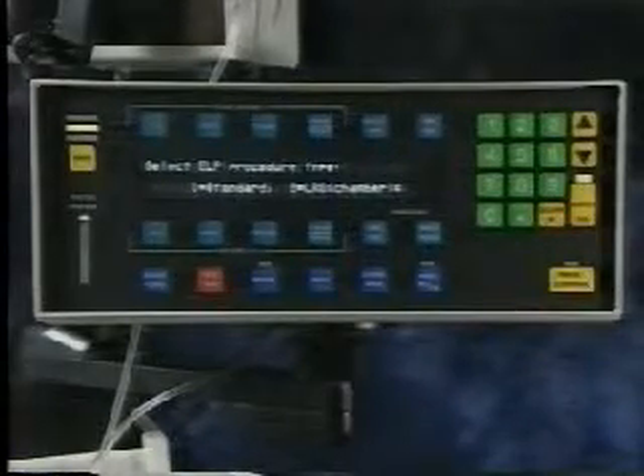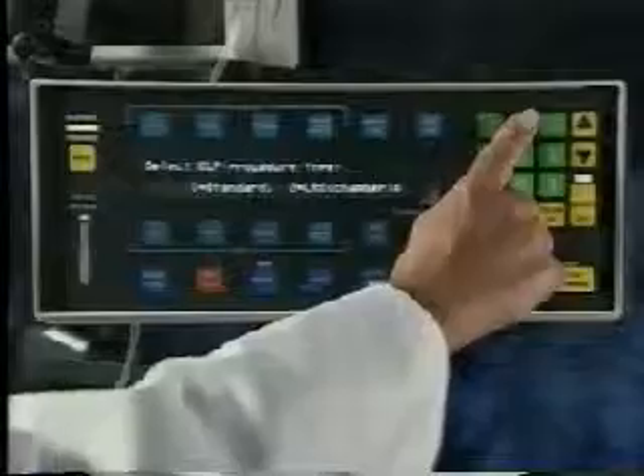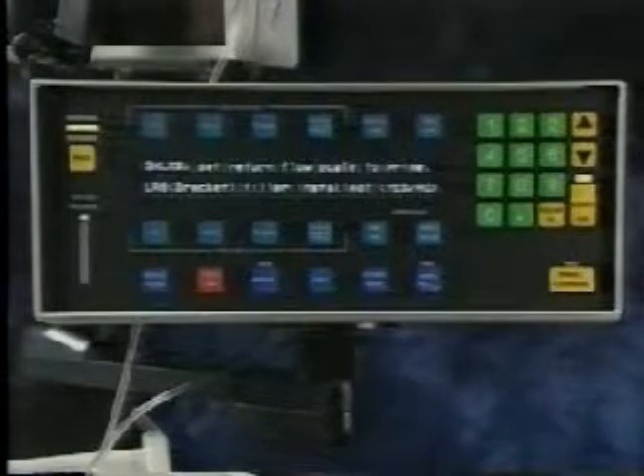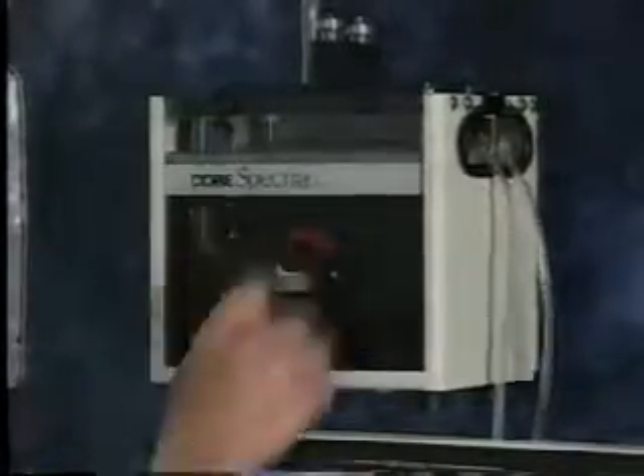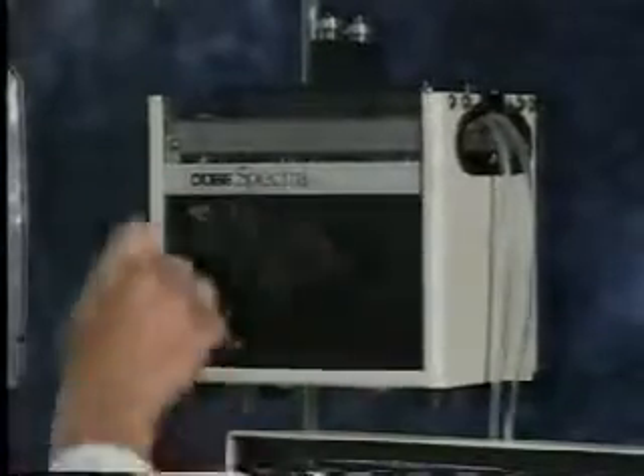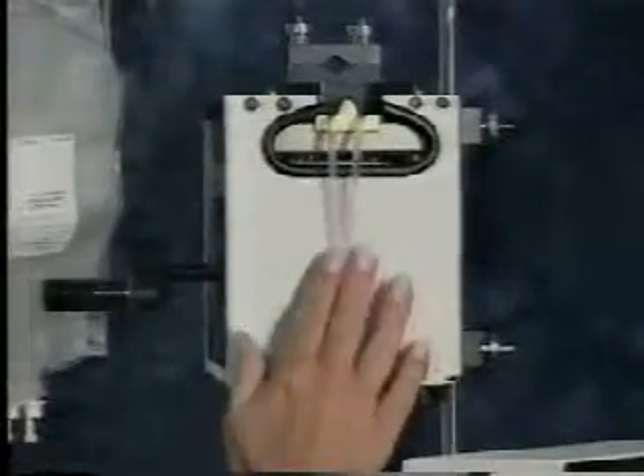Next, we need to select a standard or an LRS procedure. Press 2 to select an LRS procedure, then press Enter to confirm your selection. The system will instruct you to set the return flow controller to the prime position. Crank the flow control handle clockwise until it can no longer turn. Verify that the lines leaving the right side of the bag are not kinked or twisted. Press Yes to verify you want to continue with prime.